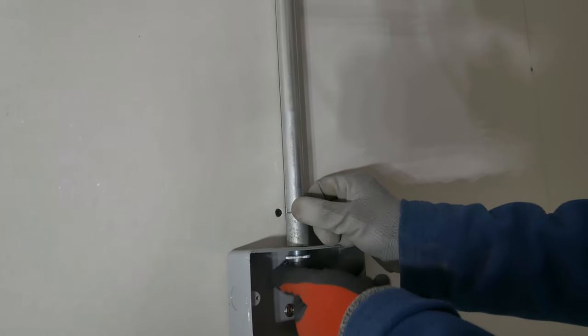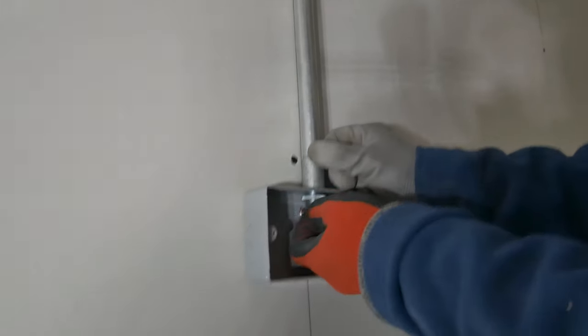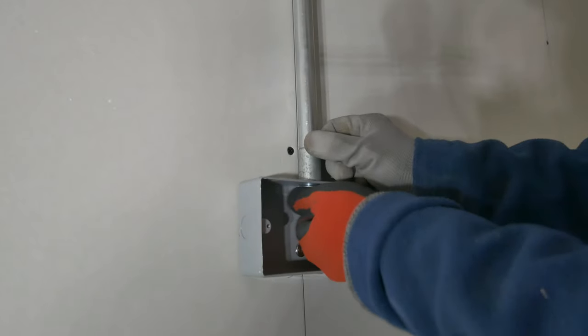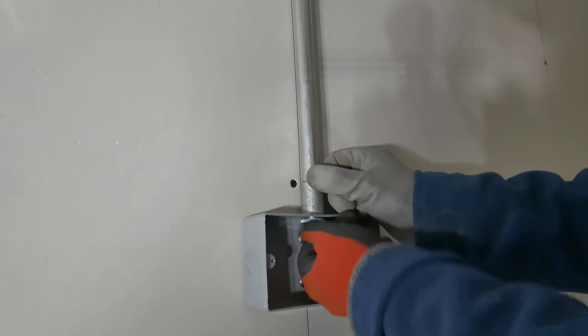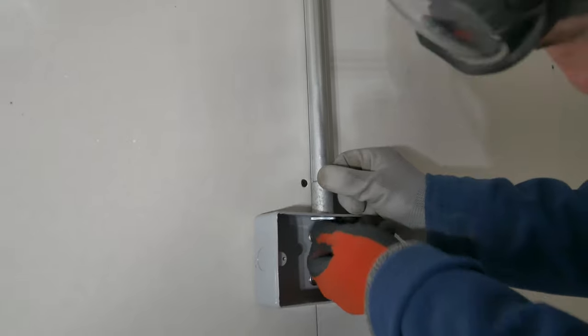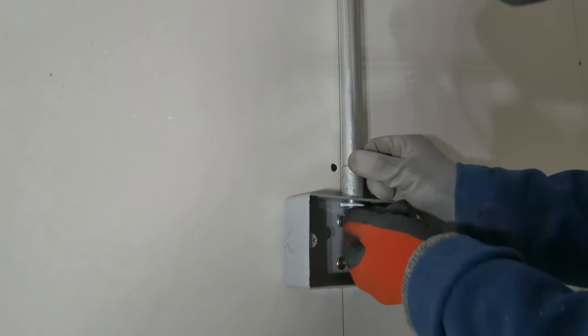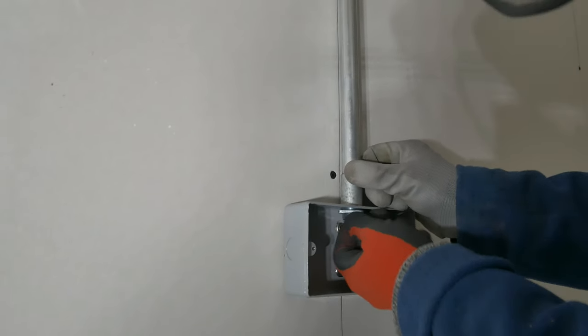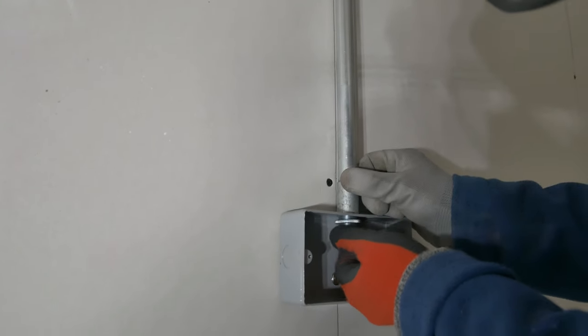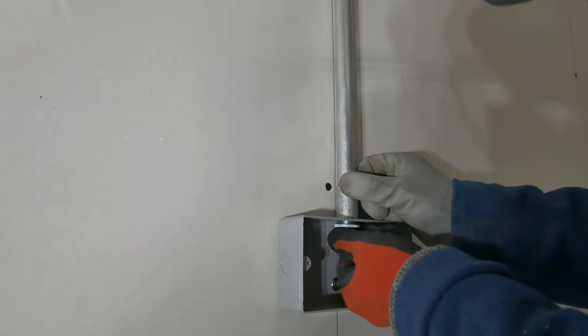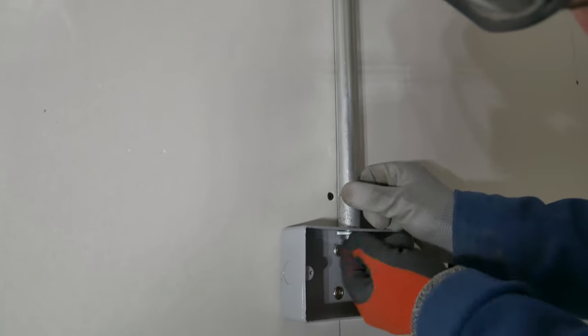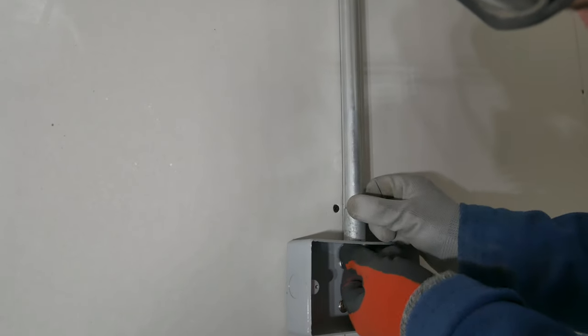And you can see he's got the hole through there now, and we're ready to start popping the tube in. Now, as I said, with this one, we're using the nipples that screw into the containment. So in this case, they're screwing into the coupler there, up into the fitting, and there is a lock ring on the underneath. And you can see he's loosening that lock ring off and just turning the nipple in as far as he can get it inside that tube, and that's to remove as much of the metalwork from inside the back box as possible.